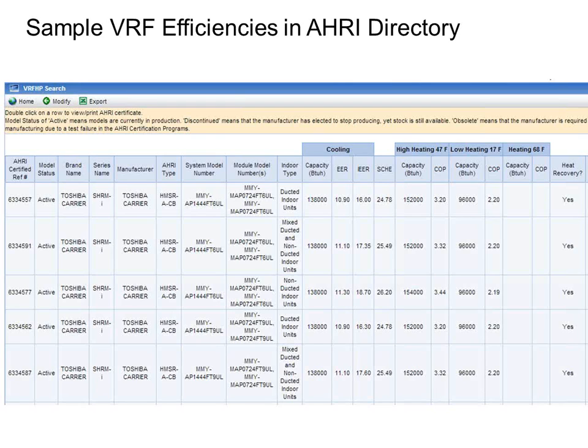So in this particular case, this is a 144,000 nominal BTU system, so it is a 12-ton system, but it's made up of 2 6-tons, 2 72,000s bolted together. I could have 2 6s, I could have a 6 with an 8, I could have 2 8s, and so on down the line. So that's why you got different model numbers there. The next thing you'll see is that indoor type. This one is very interesting. There are 3 flavors of things that'll pop up here. You'll have ducted indoor units, you'll have non-ducted indoor units, so like high-wall duct-free split type units or cassette type splits, or you'll have mixed, which means I got some ducted and some non-ducted.